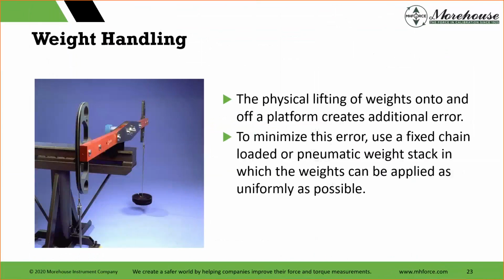The weight handling, this is a known error. The physical lifting of weights onto a platform creates additional error. The error is due to uncontrolled application of the weight onto the pan. Handling weights and placing them onto a pan may cause vibration error, tape misalignment error, and introduce a pendulum or swinging effect. If some of the arms have a twisted cable, the weights could sit there and just turn in air. So the recommendation here, which is harder to implement and gets more expensive, but to minimize it if you're concerned with it, is to use a fixed chain loaded or pneumatic weight stack in which the weights can be applied as uniformly as possible. Kind of like our deadweight systems, we can build those for torque if need be.